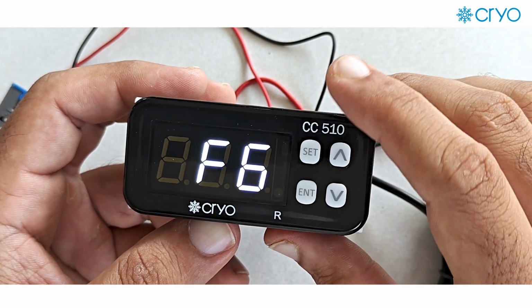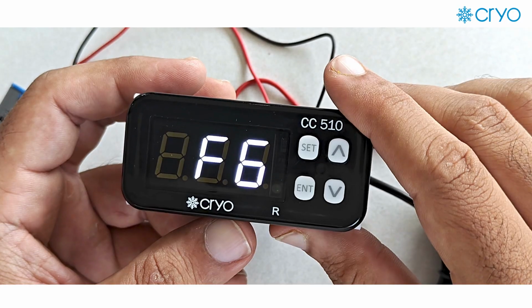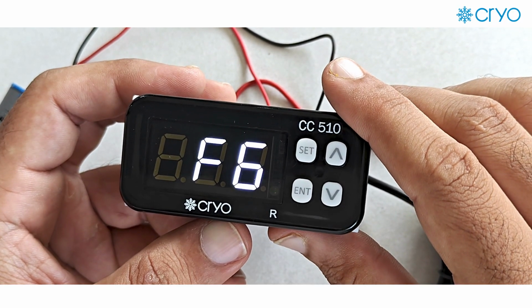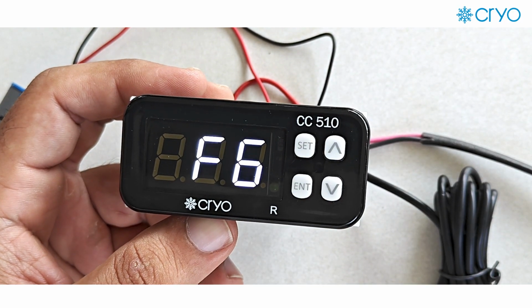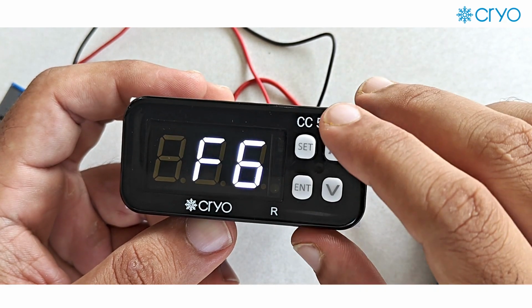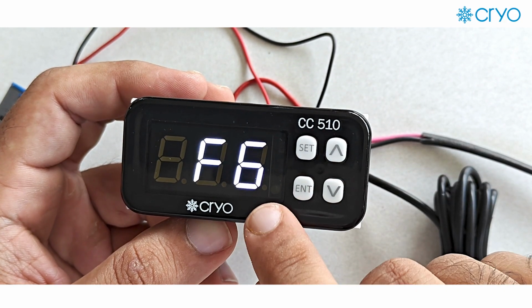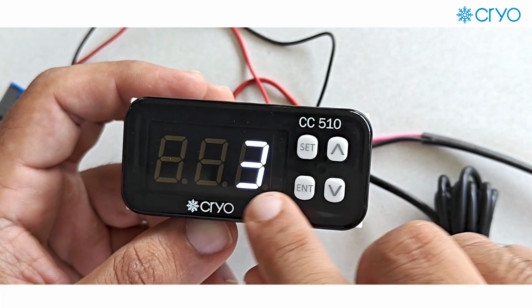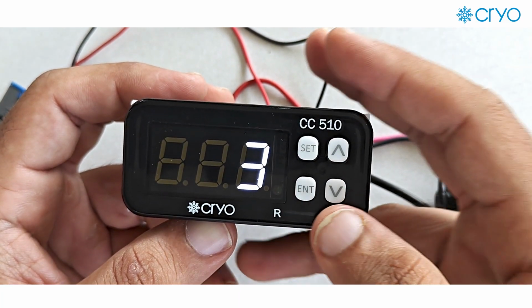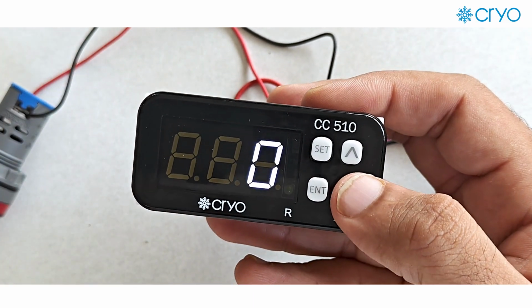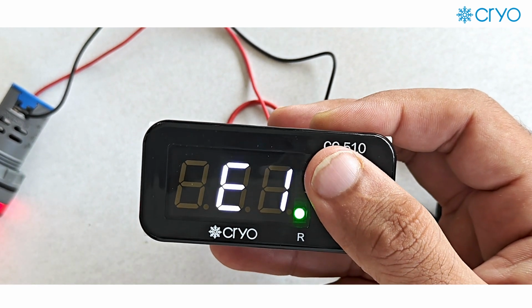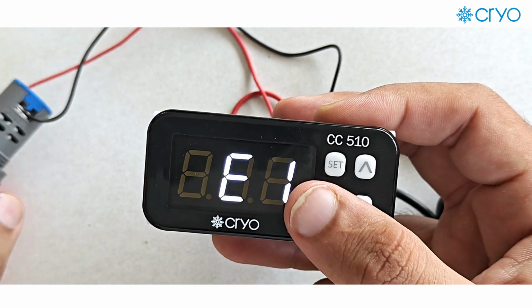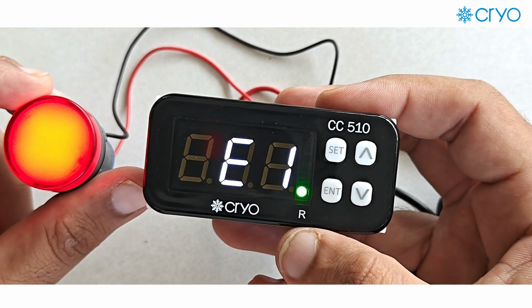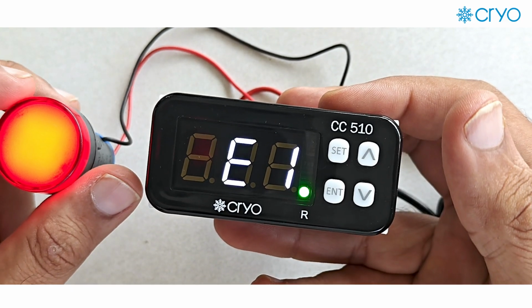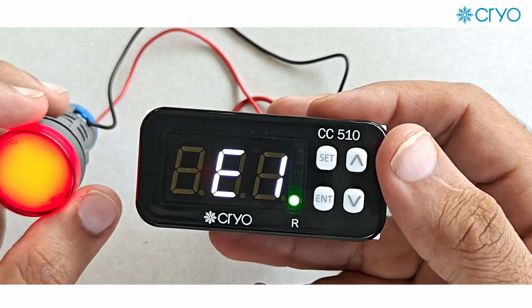Again we will press set button, F6 will come on the display. So F6 is for the time delay between compressor and relay start. So as you see, when we first power on the controller, the time delay was blinking. So by default there is a time delay of 3 minutes. If you want to make it 0, you can just make it 0 and press set button. So it will go to the next parameter. So you can see our LED has come on as the delay time we have made it 0.